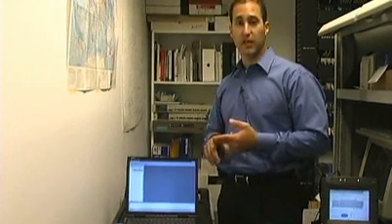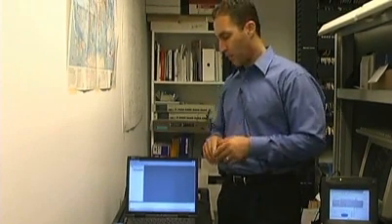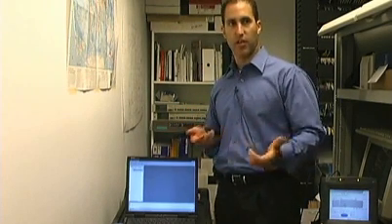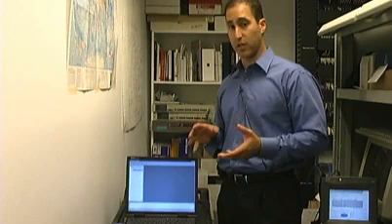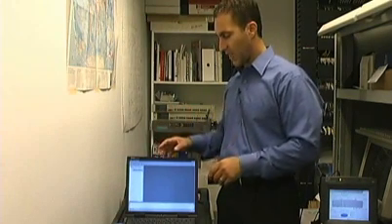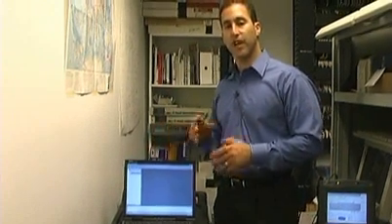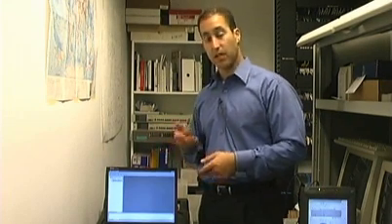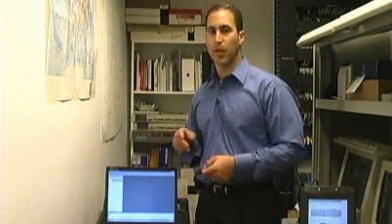And number 2, we're measuring the EIA-TIA specs. But we're measuring those specs in a little bit different way than a typical contractor, or someone using a handheld, would typically measure it. The difference is that the Big Tangerine actually measures and looks for impedance, frequency, spikes, and not necessarily averages. Your handheld devices are measuring for averages, so oftentimes we'll follow a contractor up and fail channels because it misses the spec, because they don't have that type of visibility across the channel that we can see with the Big T.